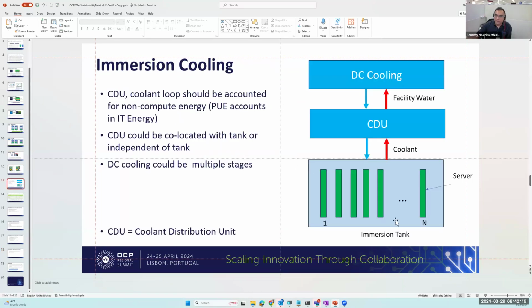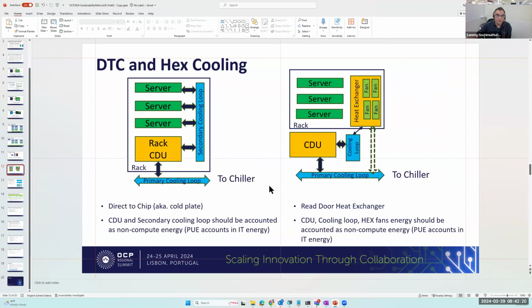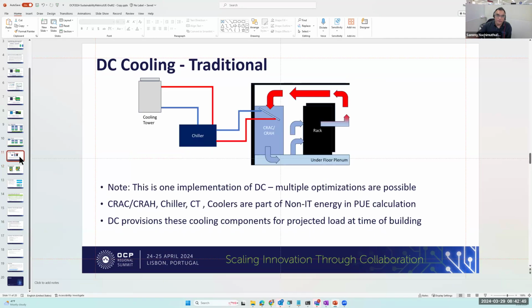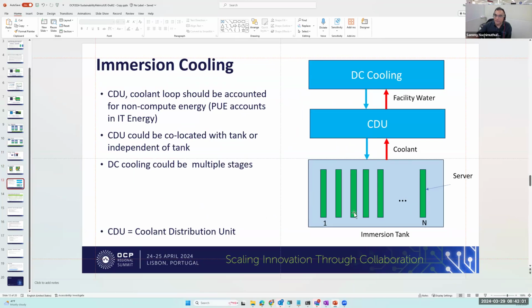Cooling distribution unit - for example, you could have a secondary cooling loop going across servers to the rack coolant distribution unit, which takes the heat out and sends it to the primary chiller. That's the traditional setup, going to towers and other coolers. But with an immersion tank, the liquid circulates and the CDU takes the heat out and sends it to the facility to cool.